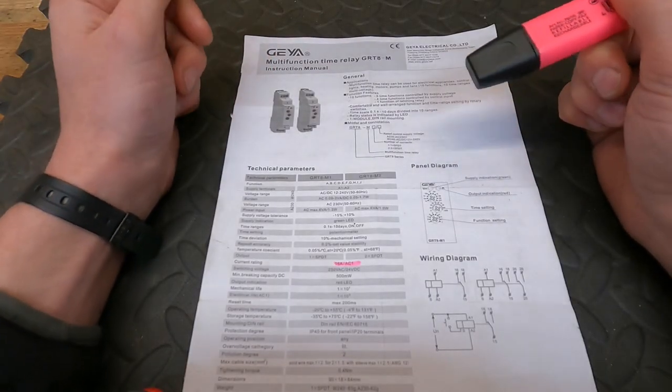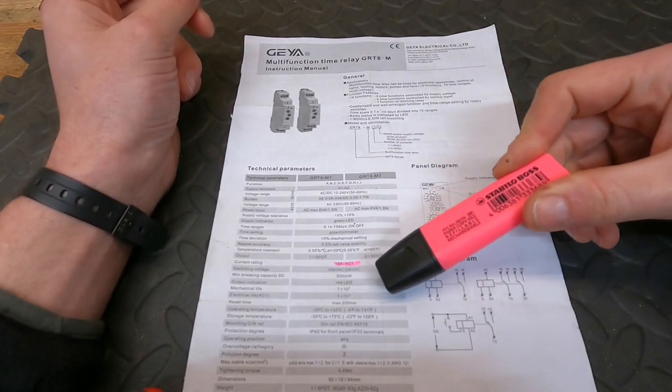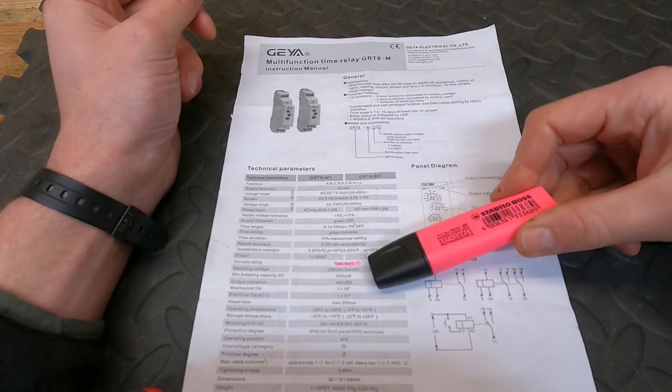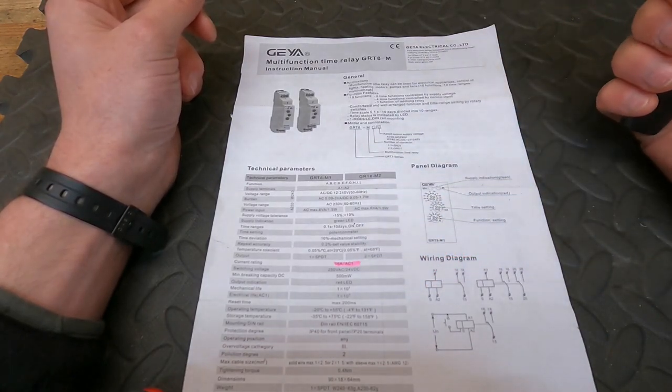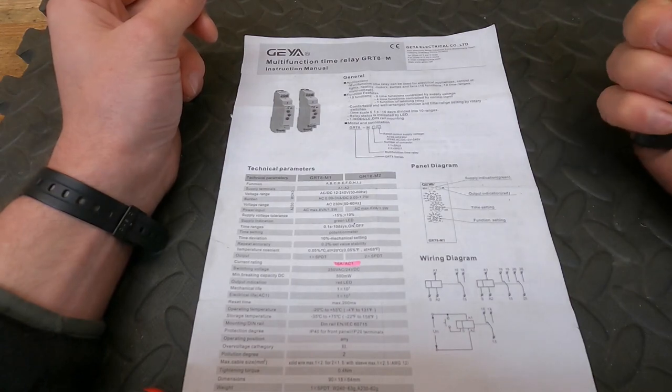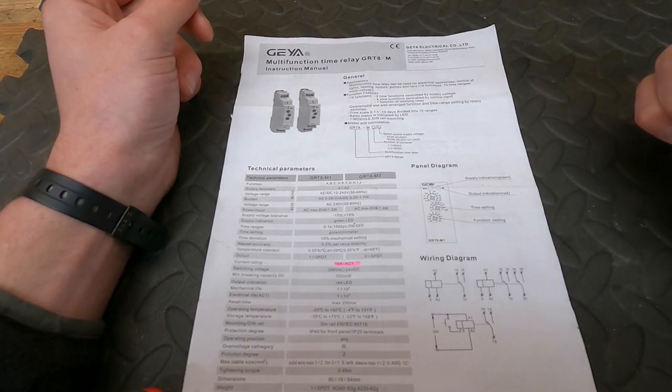This is the time delay relay spec sheet. When I was looking over it, I noticed a bit of an issue. The current rating is noted as 16 amps AC1. The AC1 part of that means that the current rating applies to non-inductive or slightly inductive loads with a power factor greater than 0.95.